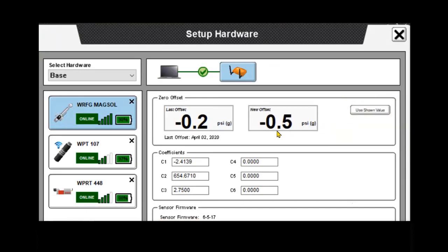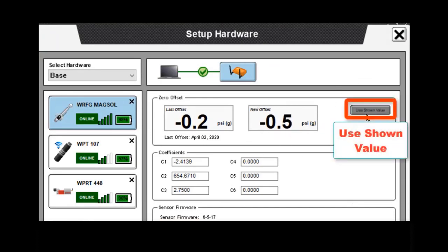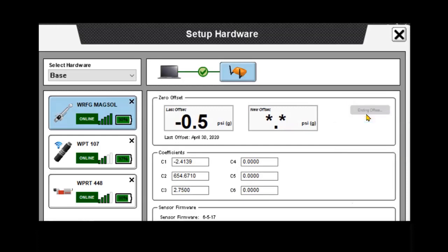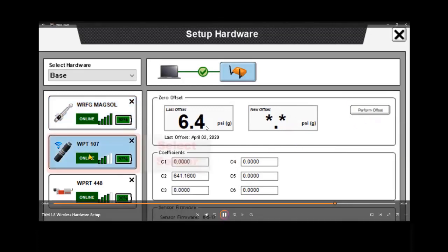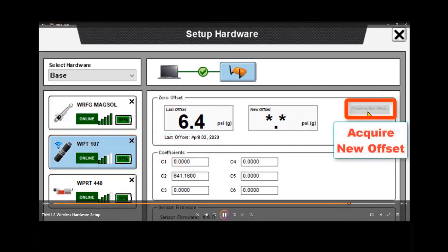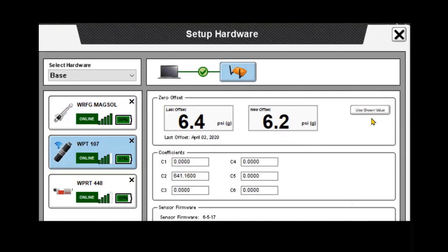So zero the pressure transducer with no pressure on it. We're going to click Get New Offset. Once we're satisfied with the offset, we're going to click Use Shown Value, and you can see how that ultimately shifted the value over to the last offset. Now we're going to demonstrate doing the zero offset on the wireless pressure transducer as well.